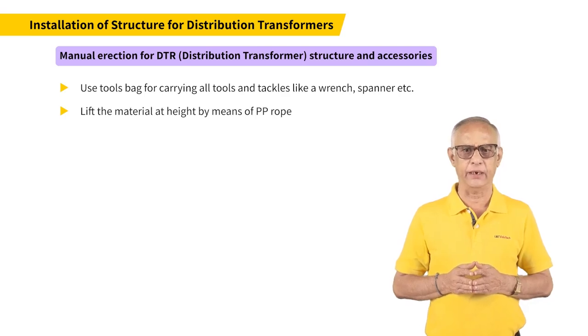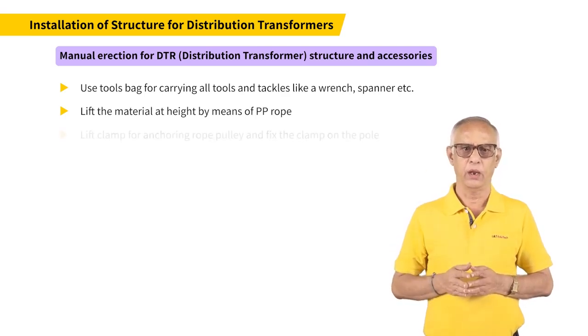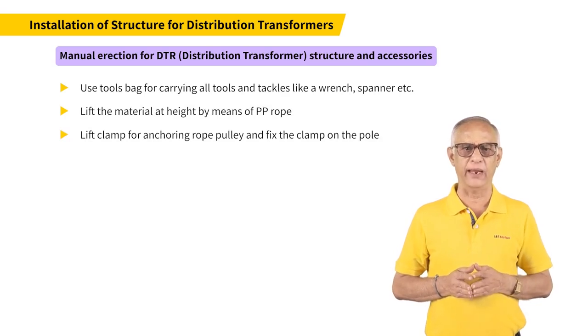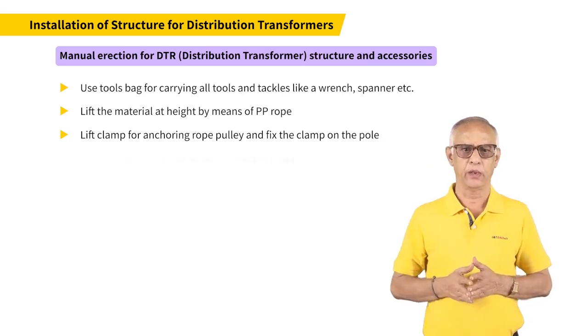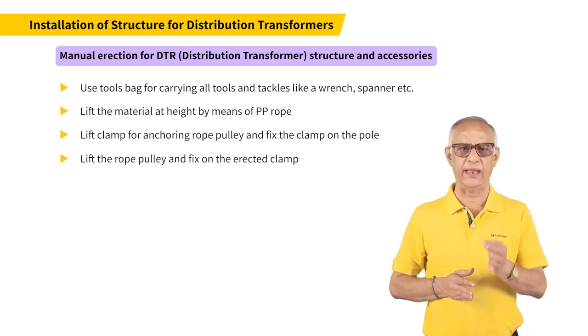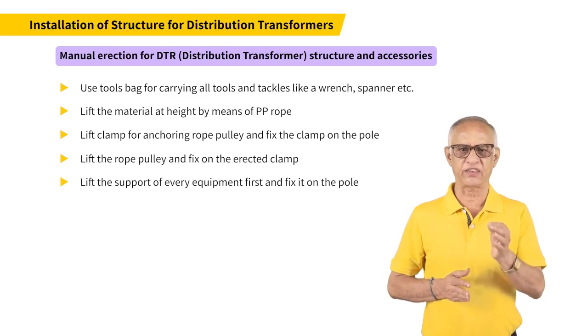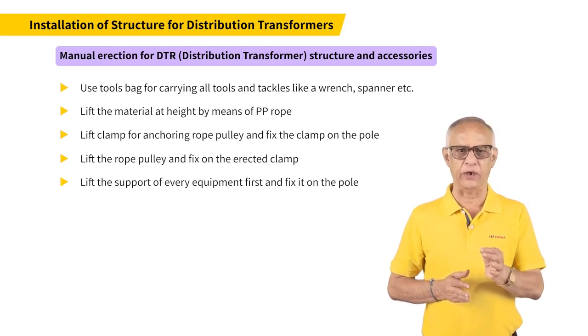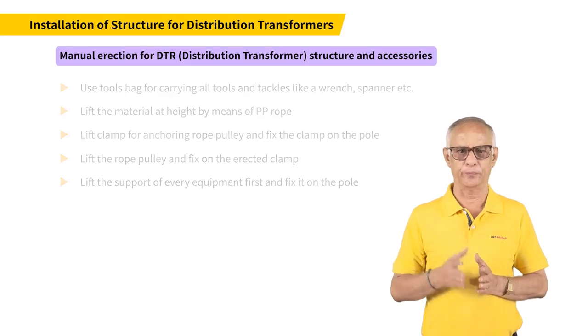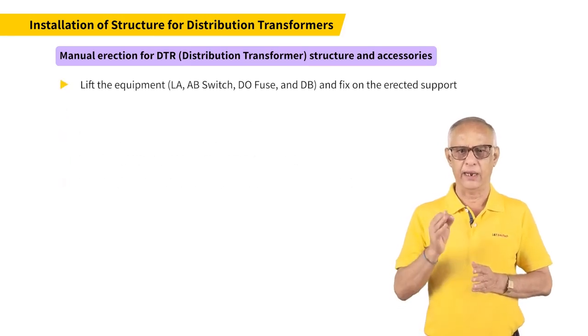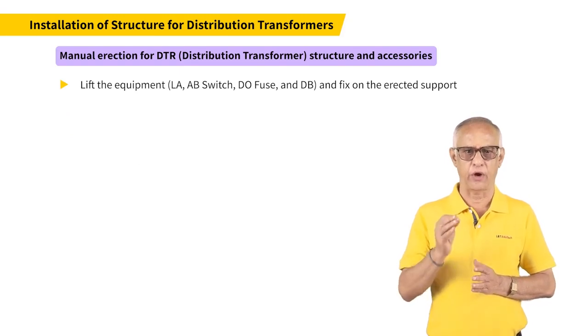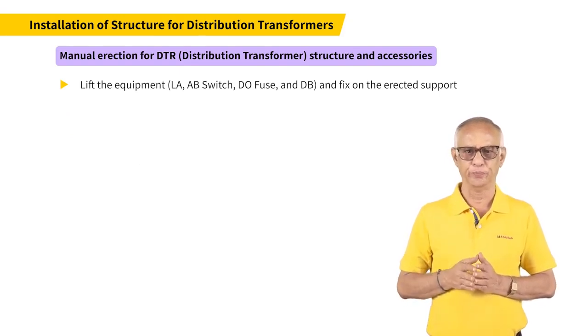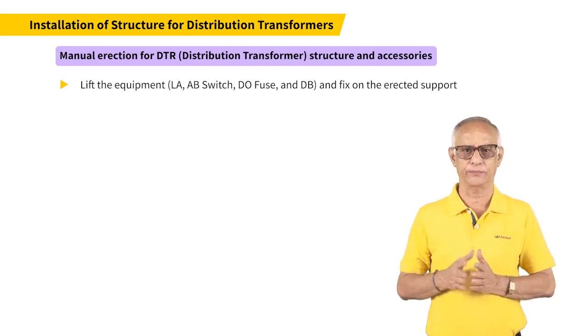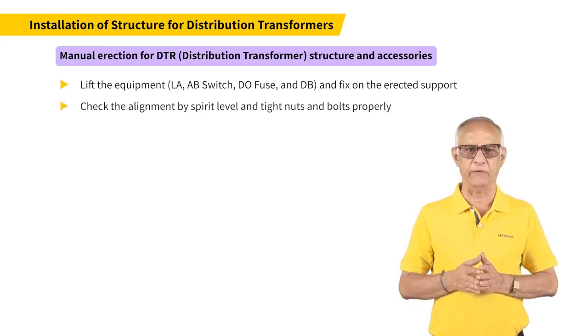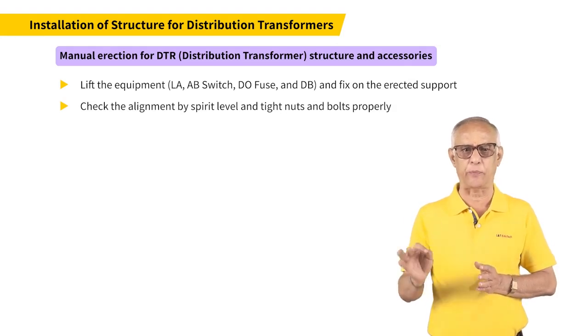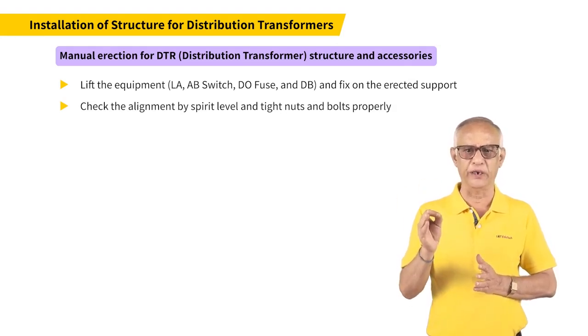Lift the material at height by means of a PP rope. Lift the clamp for anchoring the rope pulley and fix the clamp on the pole. Lift the rope pulley and fix it on the erected clamp. Lift the support of every piece of equipment first and fix it on the pole. Lift the equipment, lightning arrestor, AB switch, dropout fuse and distribution box, and fix on the erected support. Check the alignment by spirit level and tighten nuts and bolts properly. Remove all the loose materials from the height.